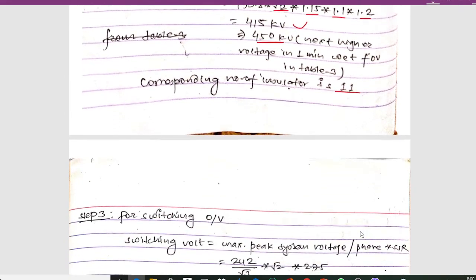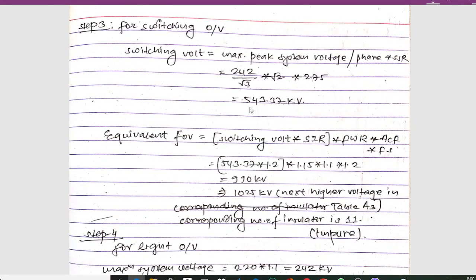For Step 3, switching overvoltage: the maximum peak switching overvoltage = (maximum system voltage / √3) × √2 × SSR. Maximum system voltage is 242 kV, divided by √3 for phase voltage, multiplied by √2 for peak, and multiplied by SSR = 2.75.